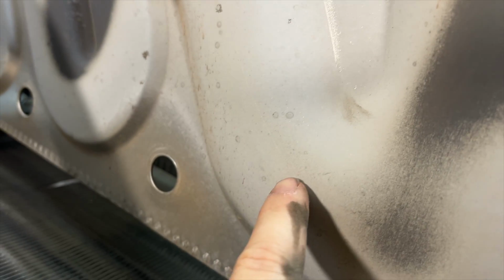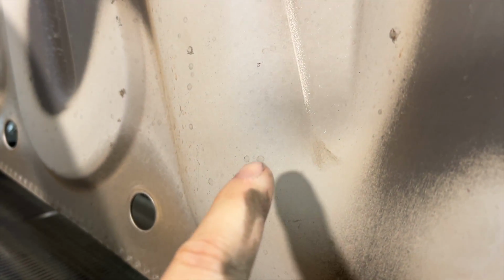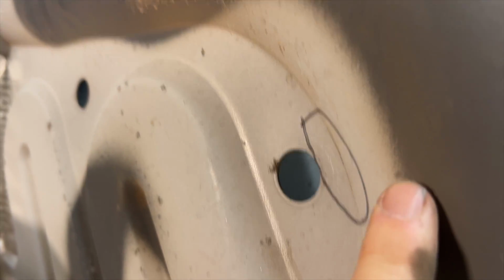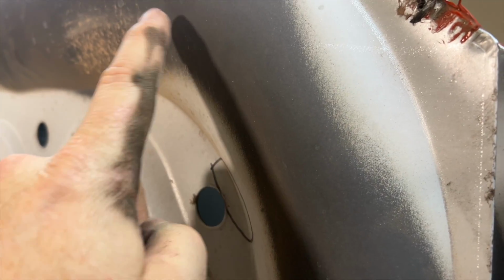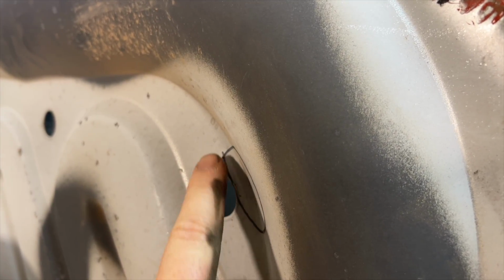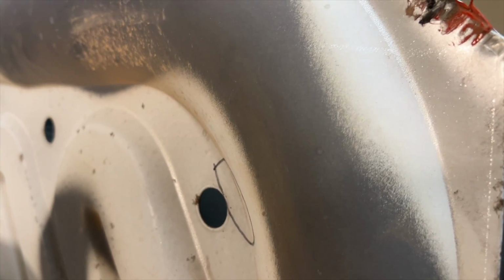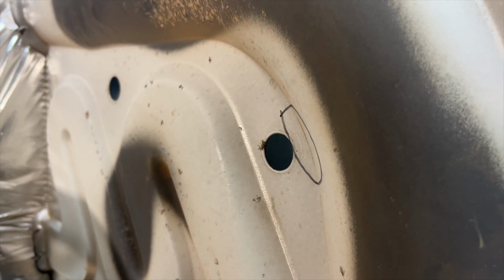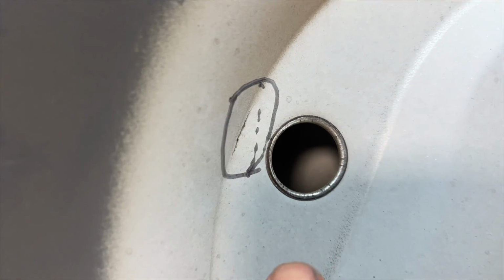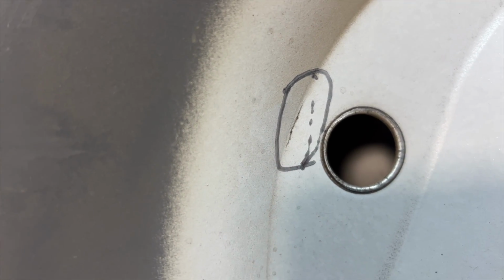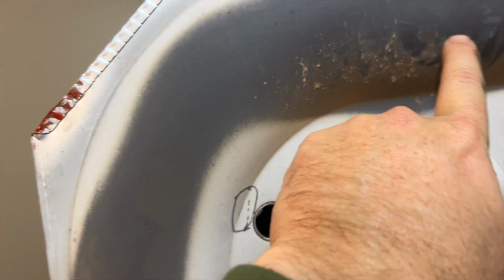Now, usually they'll be down here on a regular one, but because this is where the combustion chamber is, you can see it's right at that first bend. So generally you're gonna find them near that first bend, near the combustion chamber, because that's where the heat exchanger is at its hottest. Now you can see here, there's a tiny little crack right there. And like I said, these are the small little cracks that you're gonna find. They're very subtle. Again, you can see the temperature stress.